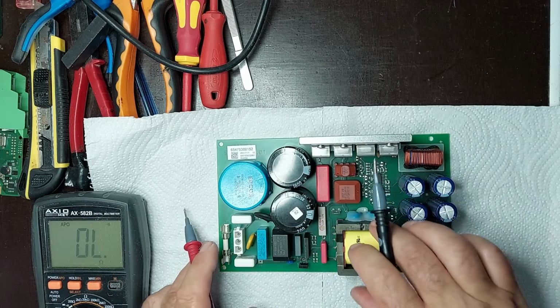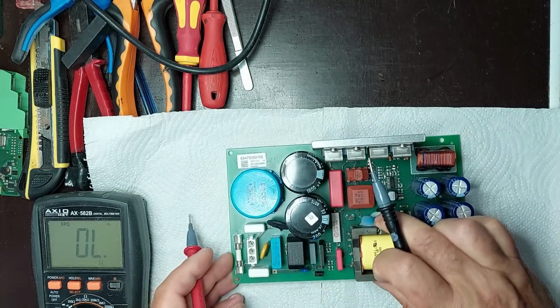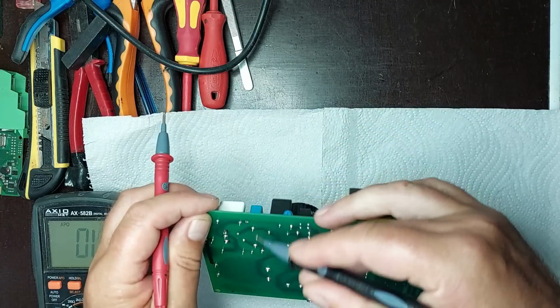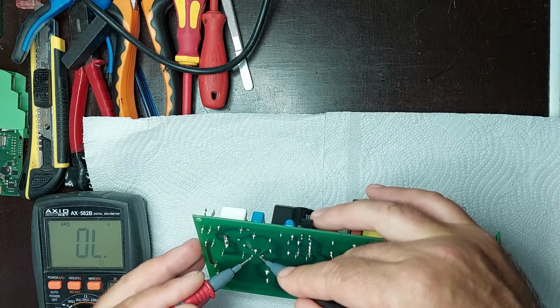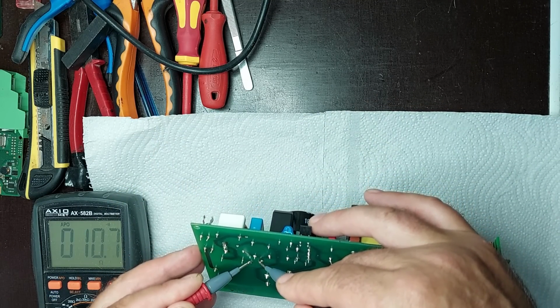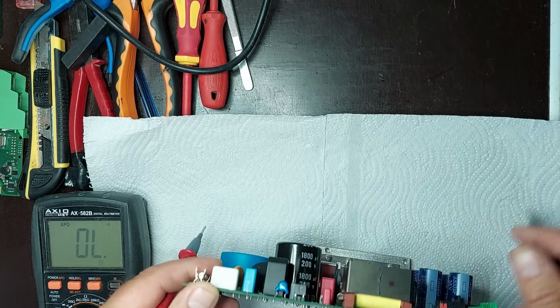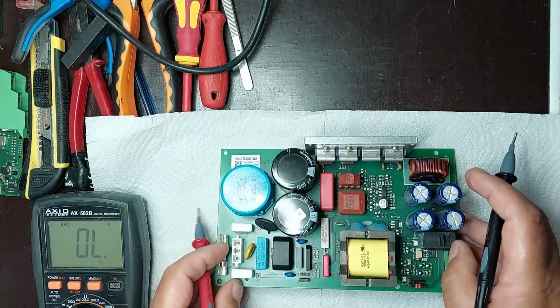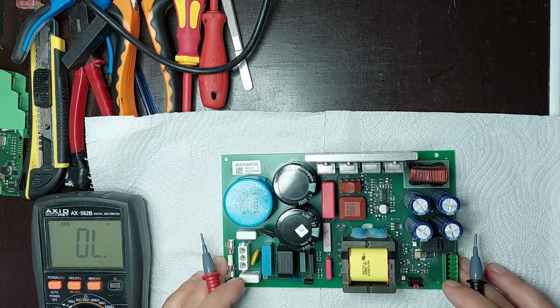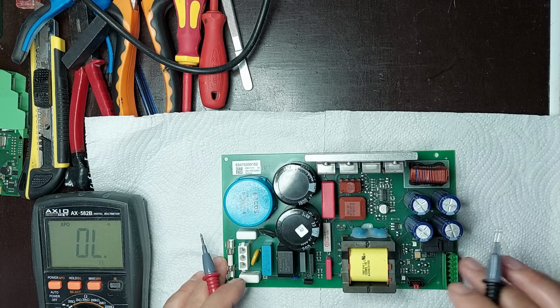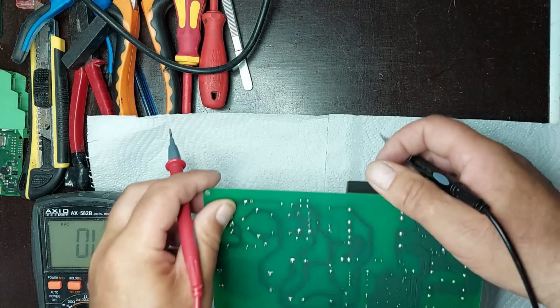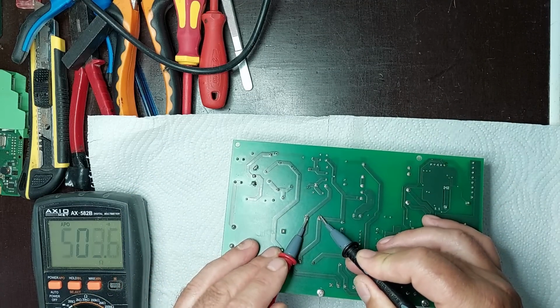I've checked the fuse, and it's in good condition. It's not blown and shows no signs of burning. So, we can rule out a triggered protection due to an obvious short circuit. I've also checked the input varistor, and it's within normal parameters. There are no signs of mechanical or thermal damage, which means the overvoltage protection hasn't been triggered.